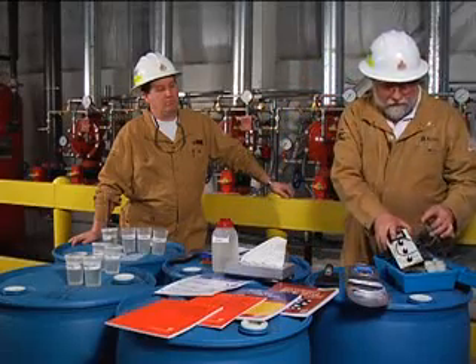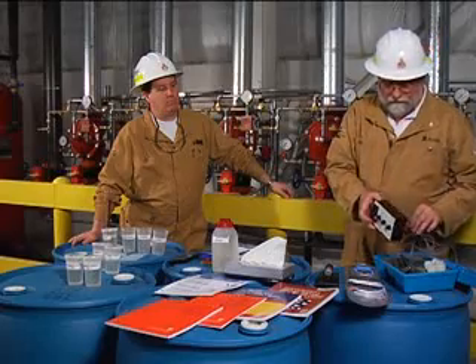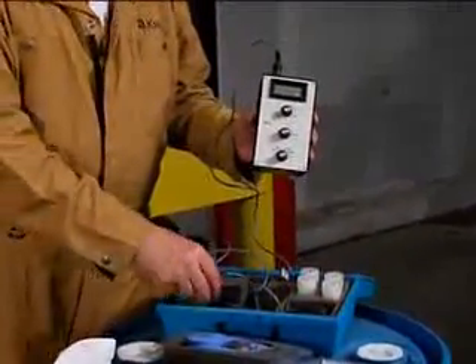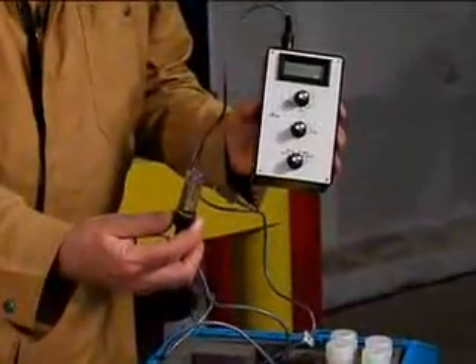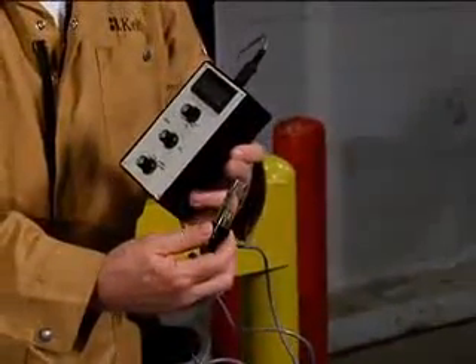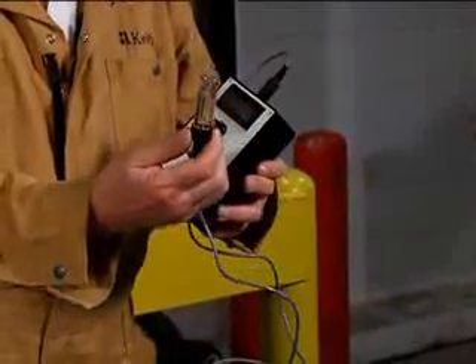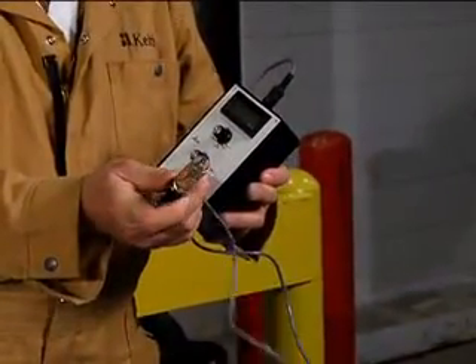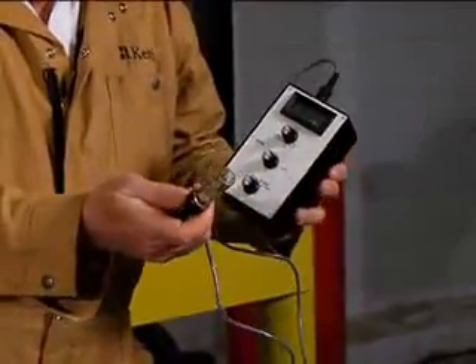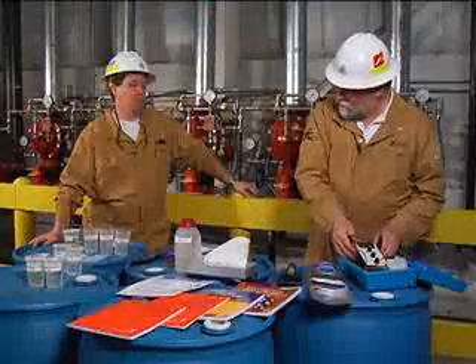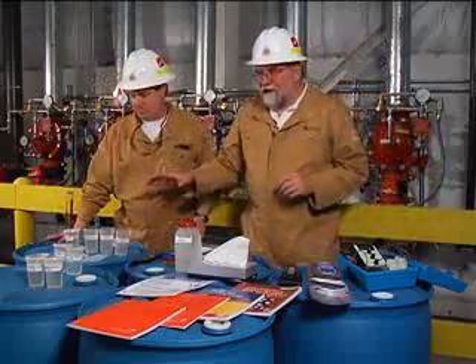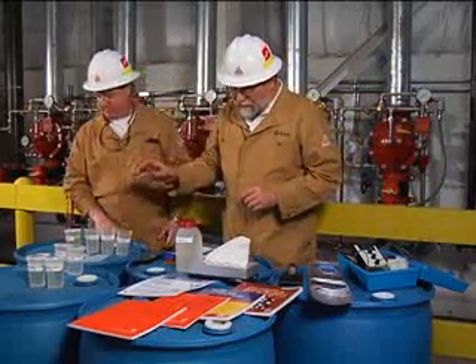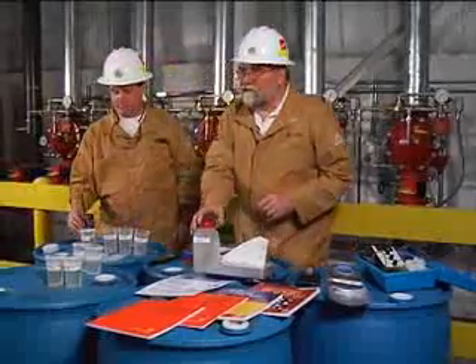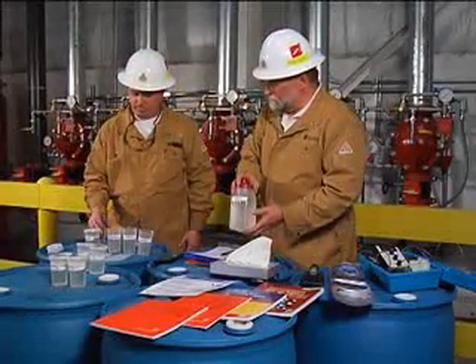The next type of instrument that we're going to demonstrate the use of is a conductivity meter. A conductivity meter has a probe, and we're measuring electrical conductance between the two probes, similar to a pH meter of sorts. First, we need to make up what we call calibration standards. Calibration standards are known mixtures exactly prepared using the concentrate and the water from the system.